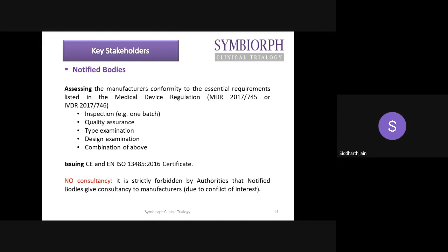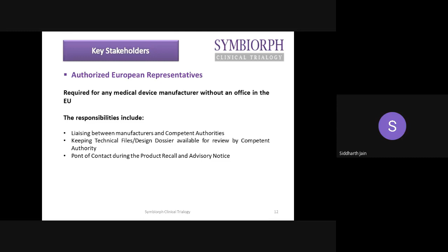Regarding the authorized representative, as I already discussed, if you don't have an office in Europe, then you have to appoint an authorized representative. Their responsibilities include liaising between the manufacturers and the competent authorities, and keeping all the technical and design dossiers available for review by the competent authorities, because the competent authority has the right to review any manufacturer's technical file or design dossier at any moment if they select it on a random basis. They will also be the point of contact during a product recall and advisory notice. That's why appointing the authorized representative is very important.